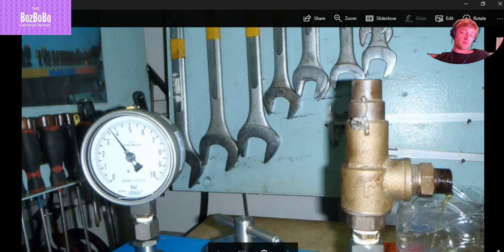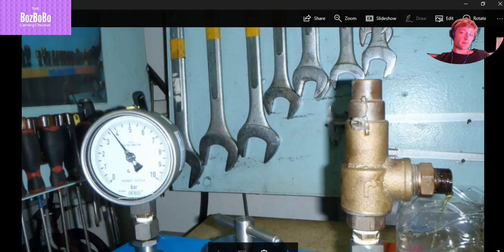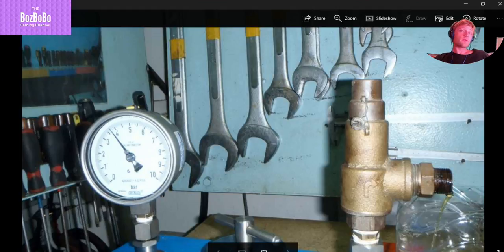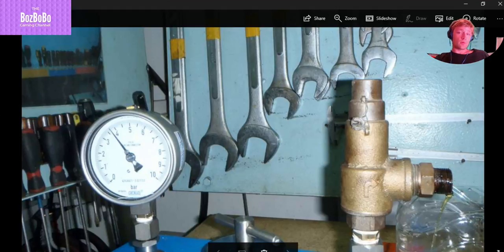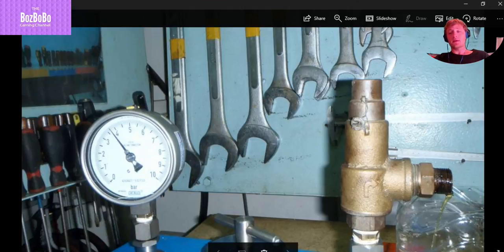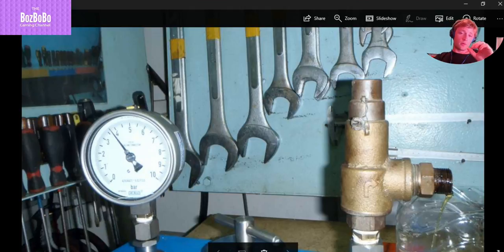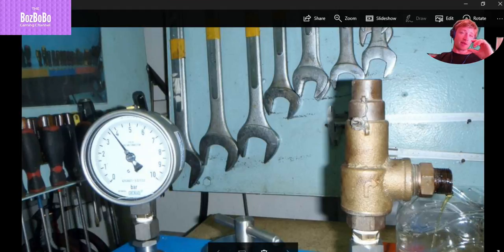And this bolt, when you make clockwise, the pressure will be increased. When you make counterclockwise, the pressure will be released, will be less. Because as we know, inside there is a spring which you adjust the tension. You adjust the tension of the spring.